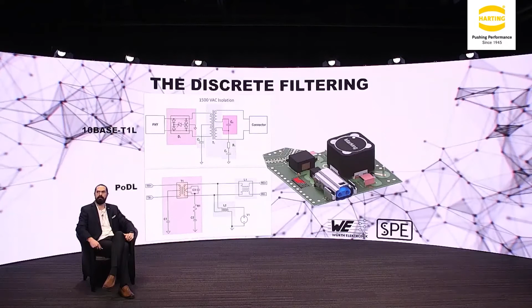Sure. In order for us to be compliant with the IEEE isolation requirement, as well as other parameters and the IEC safety requirements, we had to abandon the AC coupling capacitors rated at 50 volt, 2 kilovolt that you see here and there. Those approaches don't satisfy what the standards call for.